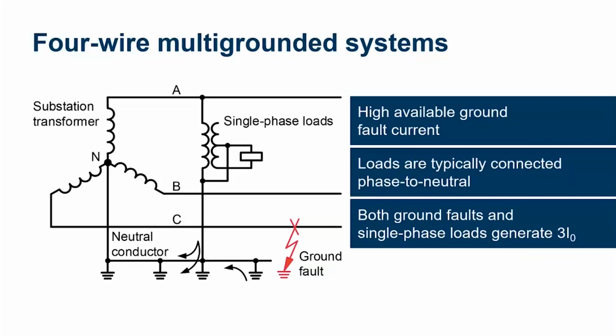Now, one of the challenges with these types of systems is that most of the time our loads are going to be connected phase to neutral. This allows us to have our equipment only rated for line to neutral voltage. However, it introduces the challenge that any imbalance we see on these systems is going to generate zero sequence current, this 3I0 current.